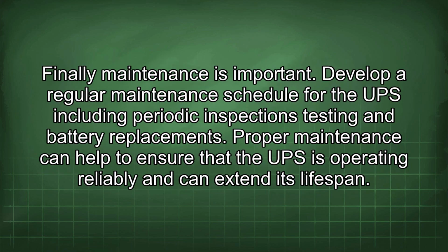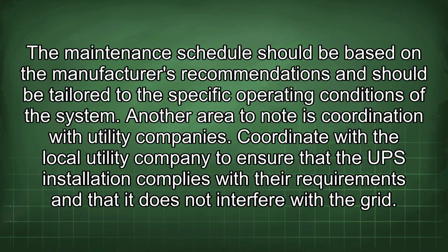Finally, maintenance is important. Develop a regular maintenance schedule for the UPS, including periodic inspections, testing, and battery replacements. Proper maintenance can help to ensure that the UPS is operating reliably and can extend its lifespan. The maintenance schedule should be based on the manufacturer's recommendations and should be tailored to the specific operating conditions of the system. Another area to note is coordination with utility companies.